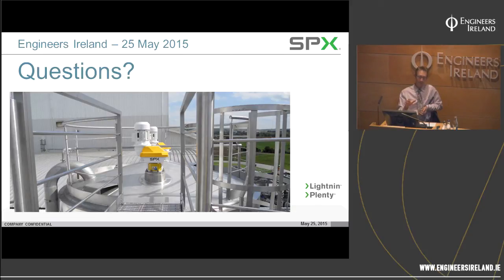That's something that when we get into the mechanical design, there are different cases. Normally a continuous process is the best case, because the liquid level's not varying, so you don't have to worry about the worst case situation where the liquid level is rising or falling through the impeller, which we know is a multiplier on the fluid force. So we have to design for that. If you've got a continuous liquid level, you can pretty much guarantee, unless it's run out of spec, that the impeller's always fully covered with liquid. So that's an easier mechanical design.